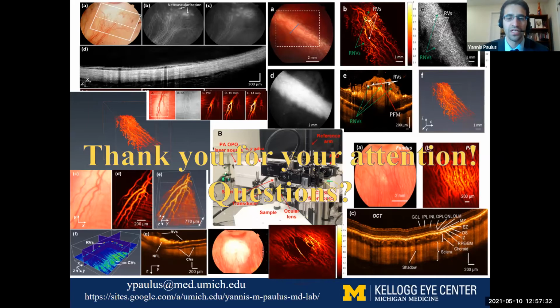But right now, to get a large volume cube like what I was showing, typically would take about a minute or so for our photoacoustic microscopy setup. But down the line, our anticipation in our newer system that we've actually developed is on the order of a couple of seconds. Photoacoustic microscopy is not necessarily inherently any slower than OCT, but in the current iterations of it, it tends to be a little bit slower, on the order of seconds rather than sub-second like OCT typically is, Jim.